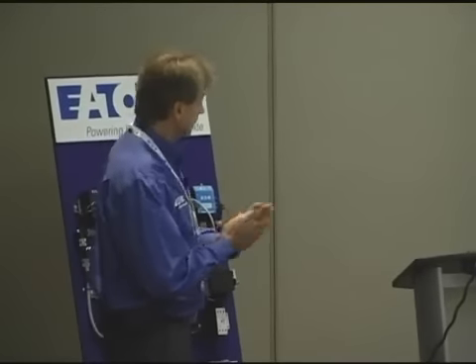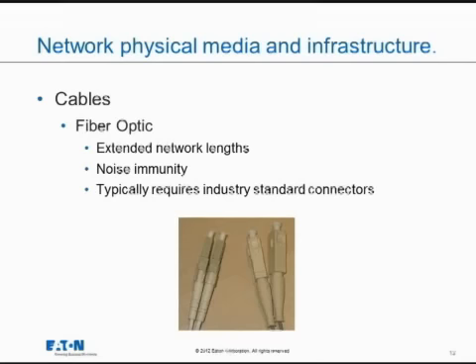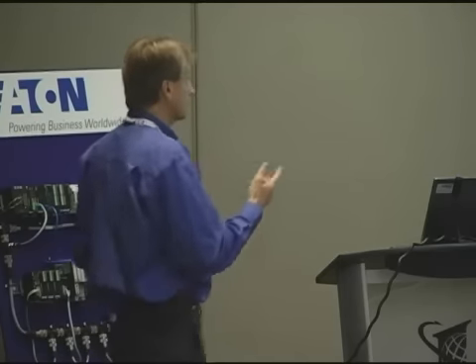Then there are fiber optic cables — still a cable, but using light instead of copper. People go to fiber optic to extend network lengths, because without resistance in the cable, light can travel much farther than a voltage signal on a resistive copper cable. The other reason is noise immunity — since we're using light, as long as external light doesn't get in, we're noise immune. Drawbacks include requiring specialized industry-standard connectors and the fact that repairing fiber optics is a specialized field. So you gain extended network length and noise immunity, but it may be harder to implement.